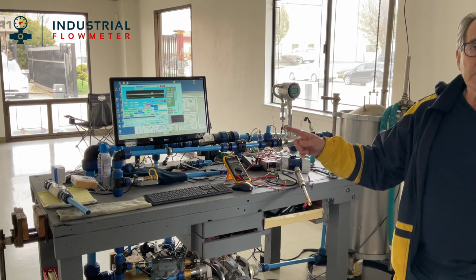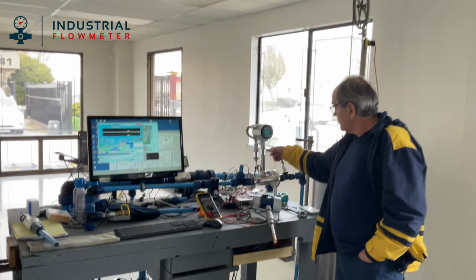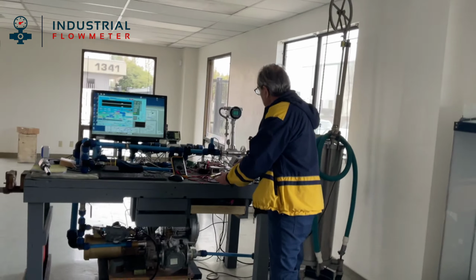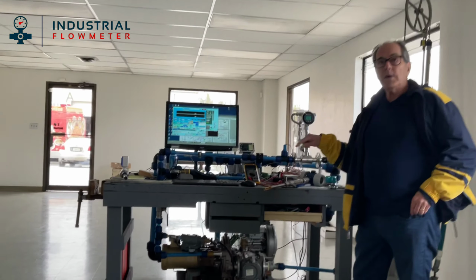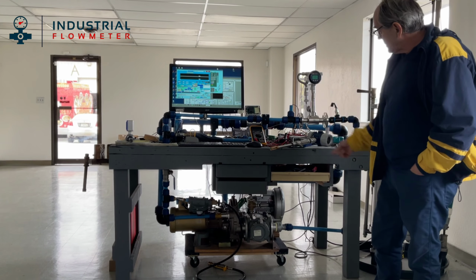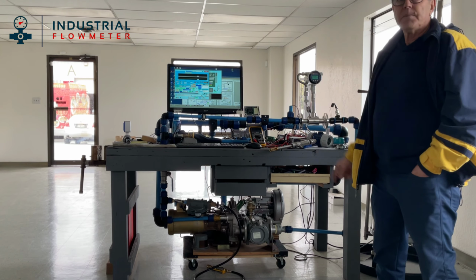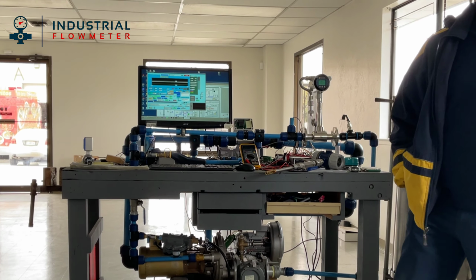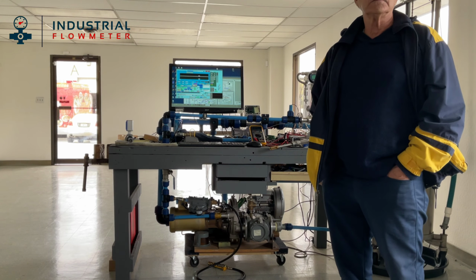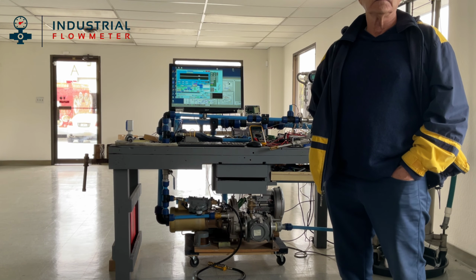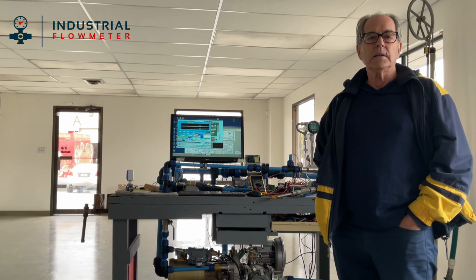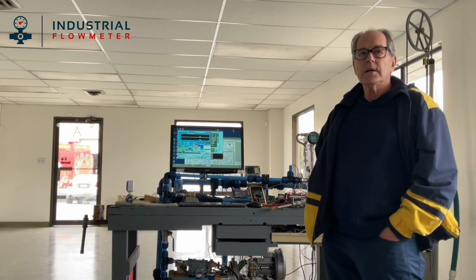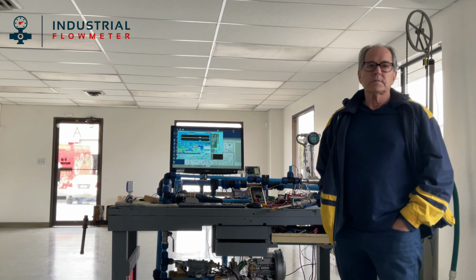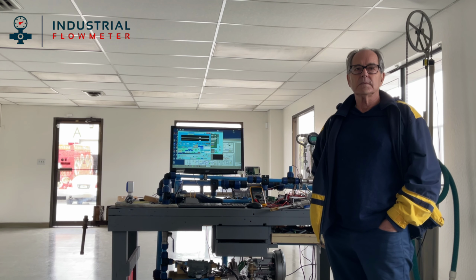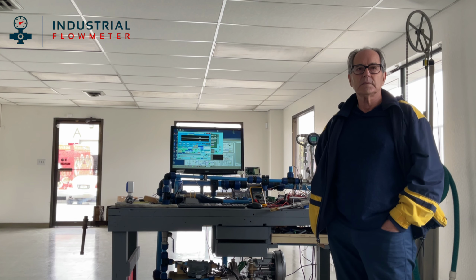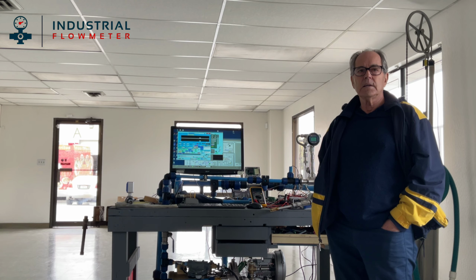That gas that you put into it, we now characterize this flow meter, or this flow meter, whatever flow meter, with that gas in this closed loop system. So I just want to back up here, and this lets us know exactly how much flow is flowing through the system, and then we can use that to calibrate. Is that accurate? Yeah. This is basically a really, really good calibration system that we can use to find and subtract out any of the errors in the flow meter.